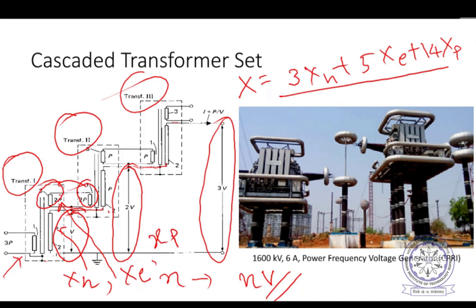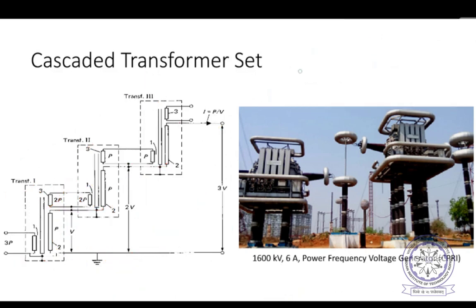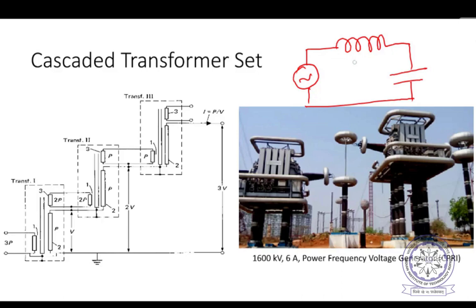What will happen if the reactance gets magnified and you are testing a cable? Cable, as I told you, is a capacitor. Now this huge inductance and the cable capacitance will be in series. Therefore, that may cause resonance at a particular frequency. So I'll show you. The equivalent will be a high voltage source like this, then a huge reactance, inductance, then capacitance like this. This may cause resonance at power frequency also, depending on the length. If not at power frequency, some harmonics may also get multiplied.